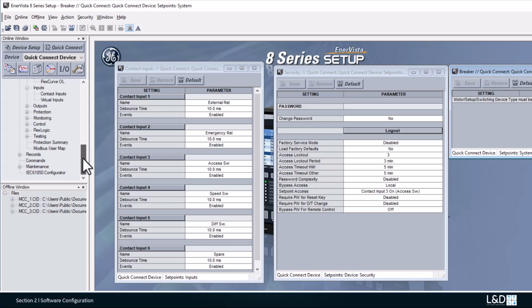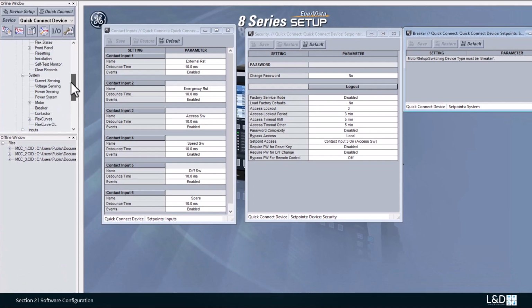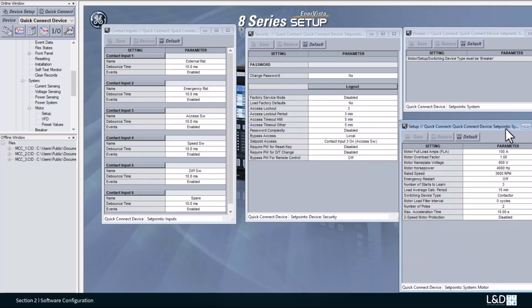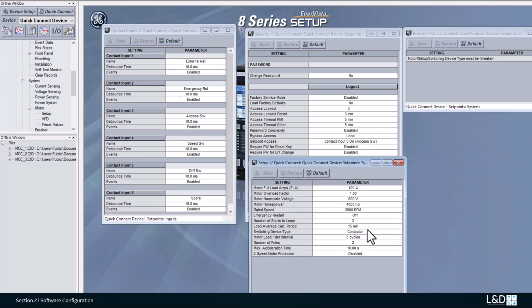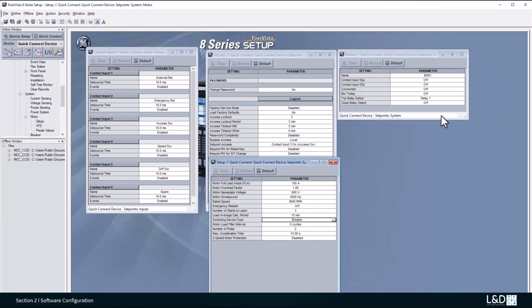So the switching device is also under the device motor setup, and sets the switching device to be breaker or the contactor. And then for the 52 switch, we can set this as a spare. That's usually what we do in the 369.